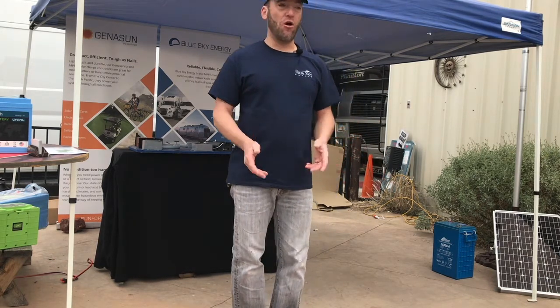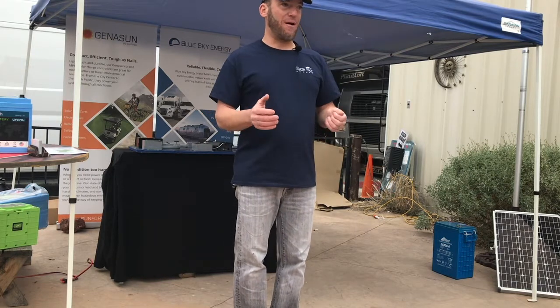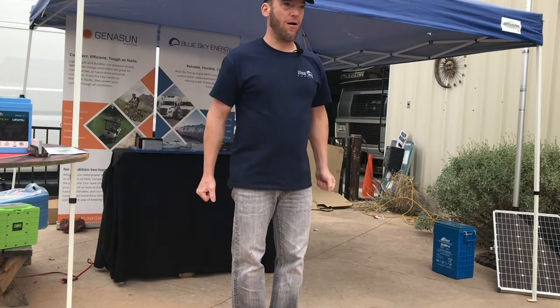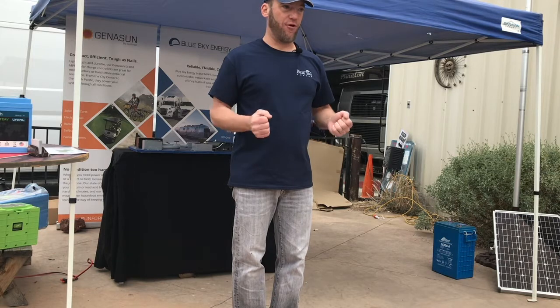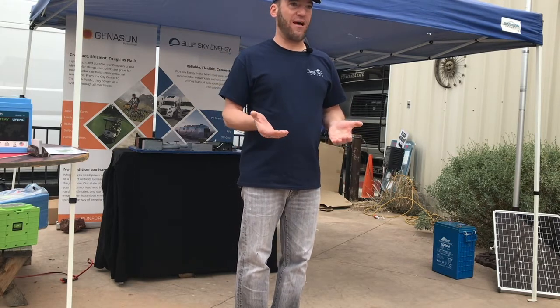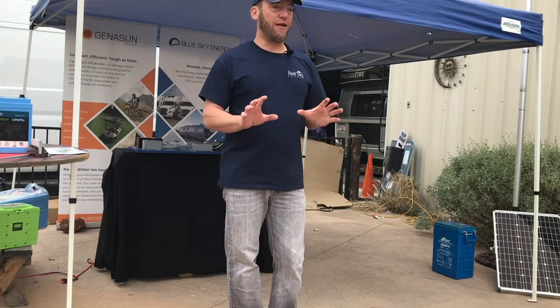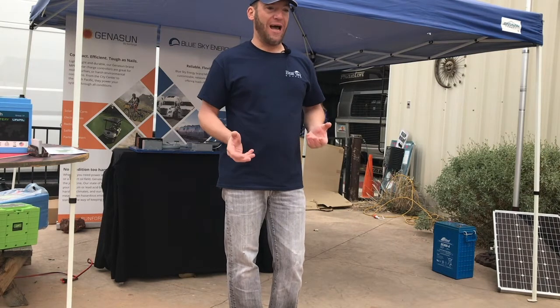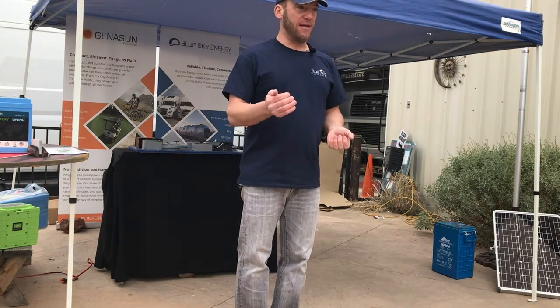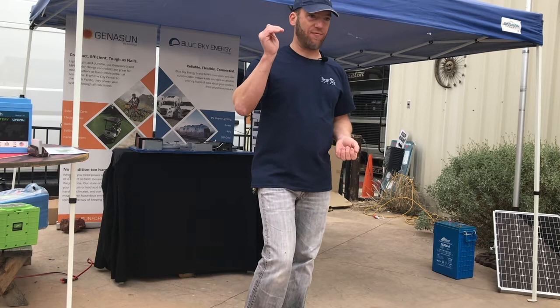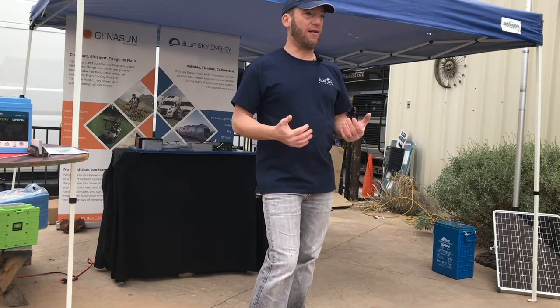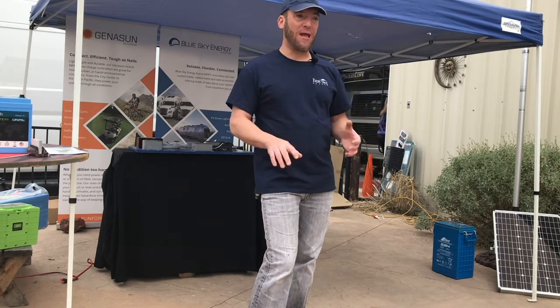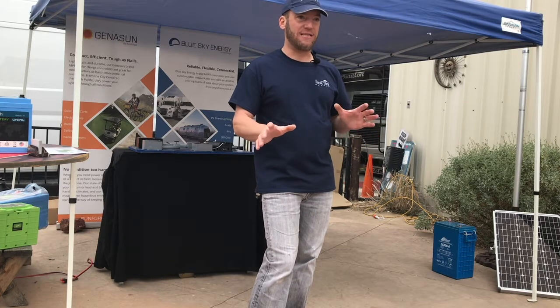With a lithium battery, you don't traditionally float it. A lead acid battery, you're always providing some power to keep it at 13.2, 13.4, to maintain it above its resting voltage. You don't traditionally float a lithium battery - you don't want to have to provide current to maintain the lithium battery above its resting voltage. But a lithium battery's initial resting voltage is like 13.6, 13.6 and a half.